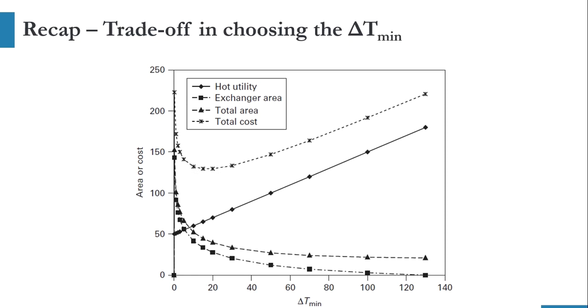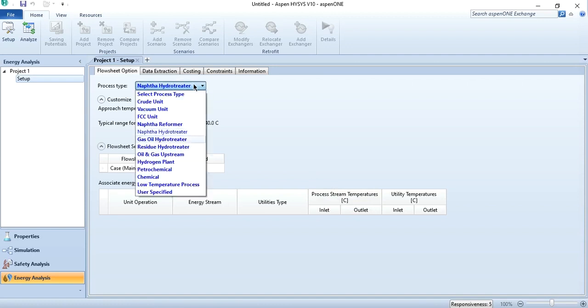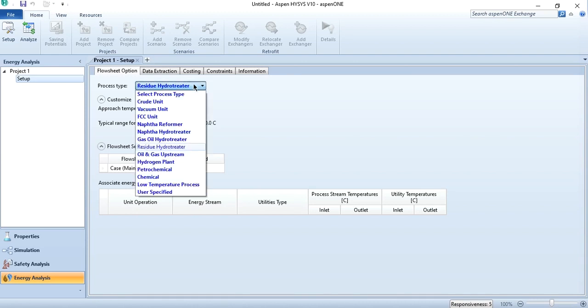But that is not always true — it varies from process to process. In the vacuum unit, this value goes from 20 to 30 degrees centigrade, while in the crude unit it was between 10 to 25. For the FCC unit, this value may vary to 30 to 40 degrees centigrade. And for naphtha reformer, naphtha hydrotreater, gas oil hydrotreater, and residual hydrotreater — these are all of the same classification — so the approach range is from 30 to 40 degrees centigrade.